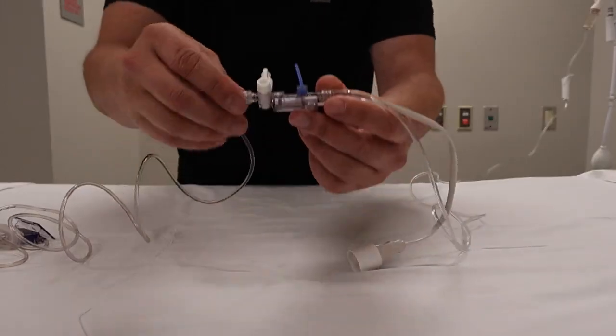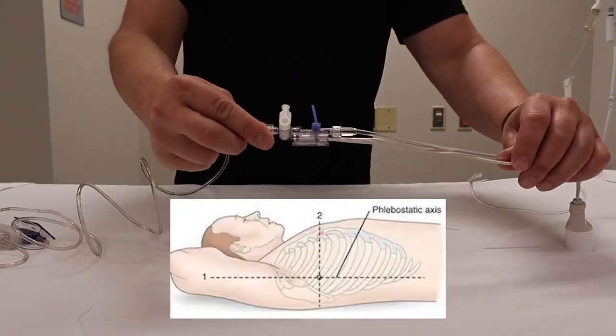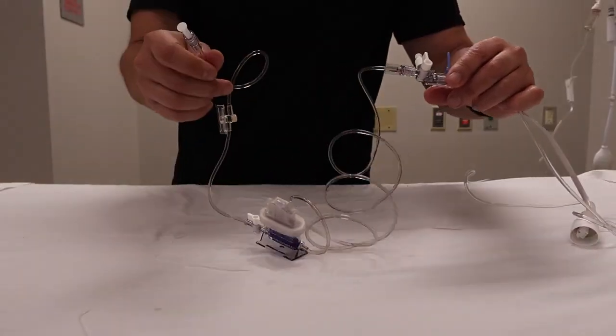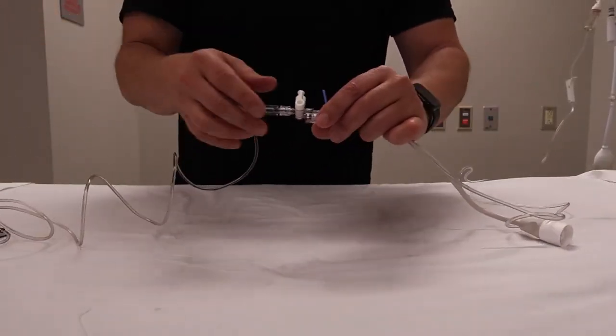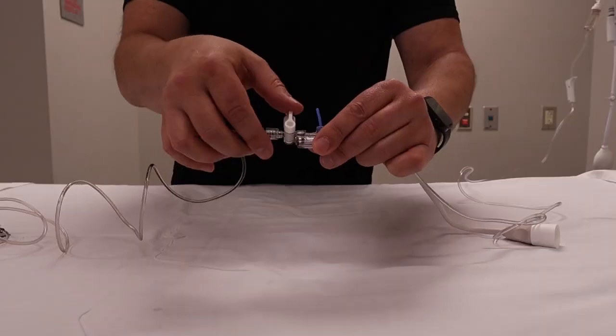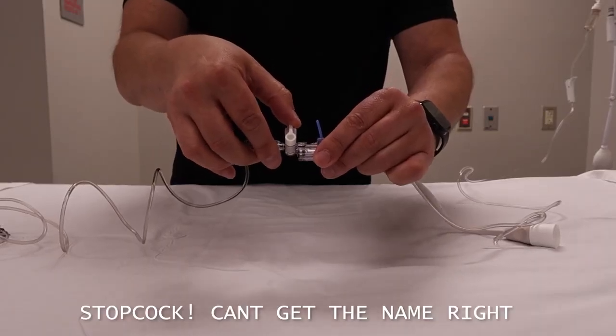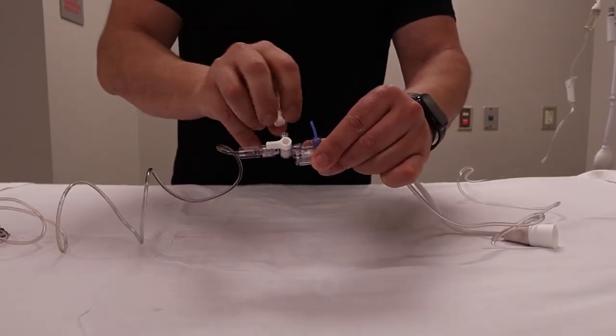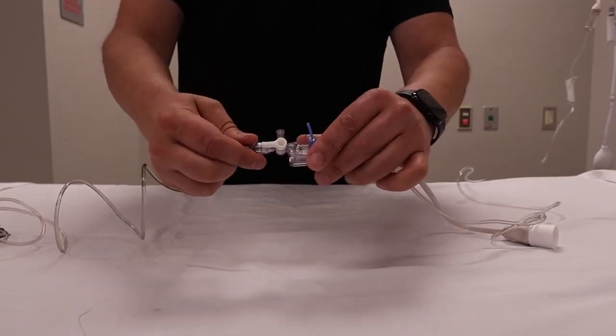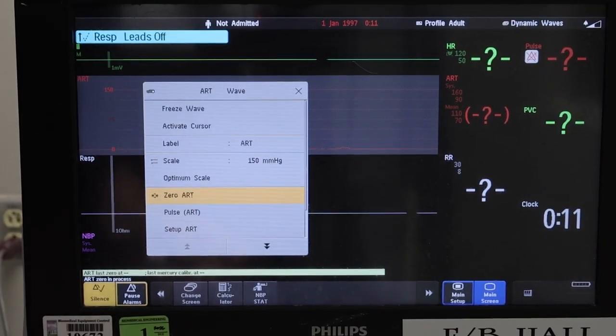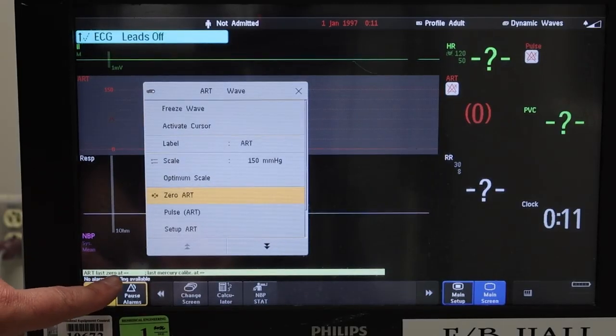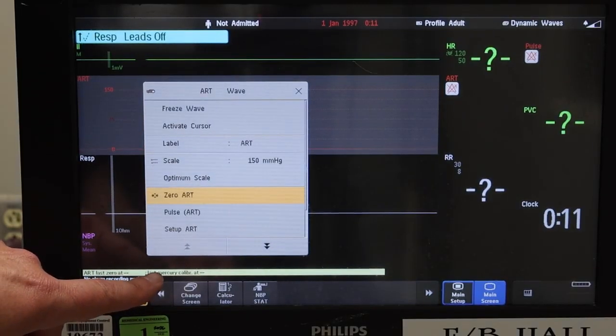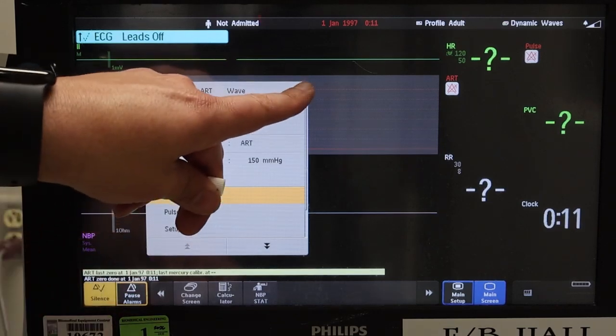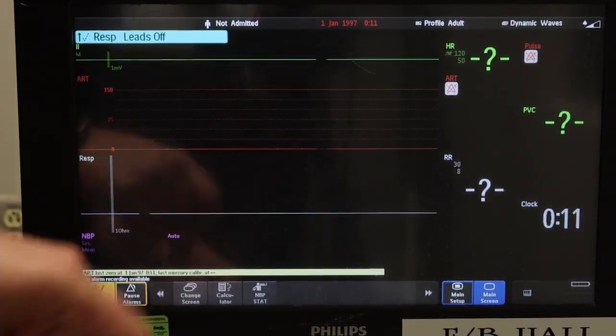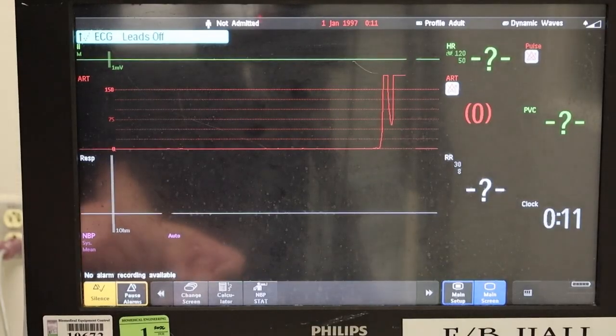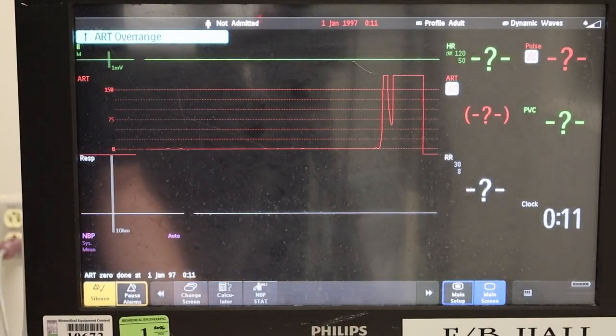When zeroing your A-line, place the transducer at the phlebostatic axis. This part goes to the patient. So take your switch here, turn it off to the patient, open it to air, zero art line. Once the zero button is pressed on the monitor, you'll see a date and time flash that should be recorded in the MAR. You should zero your A-line at the initial insertion, anytime there's a position change of your patient, and at the beginning of every shift.